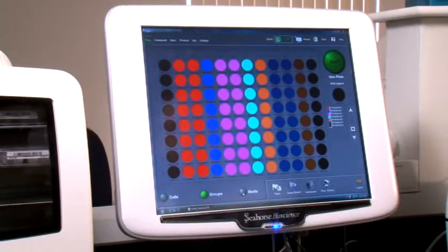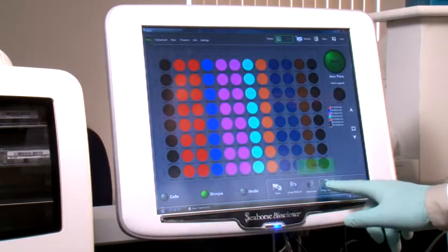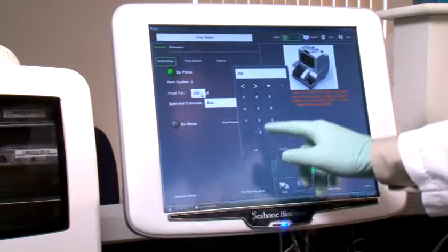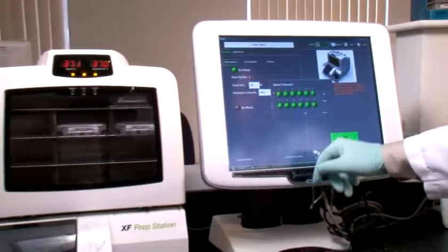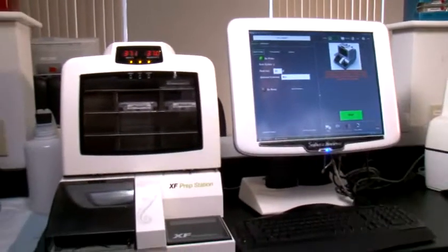Now, these steps can be automated. Using the existing application software on your XF analyzer, simply program the medium wash protocol, load your medium, and the XF prep station does the rest.